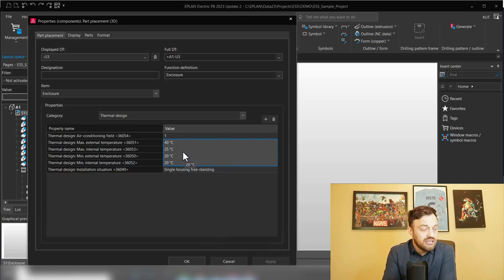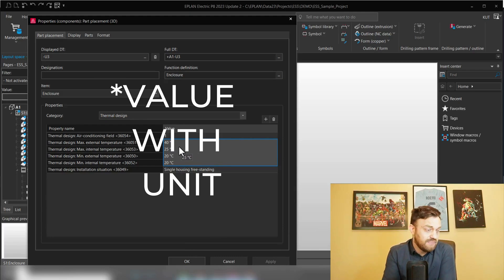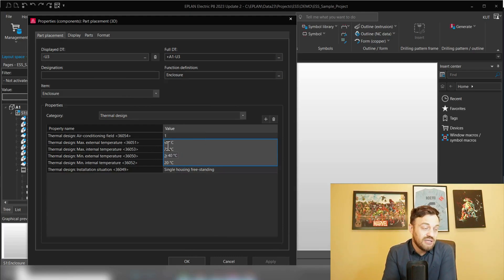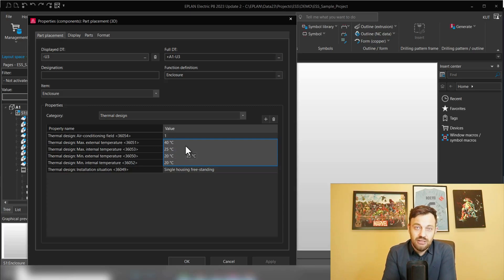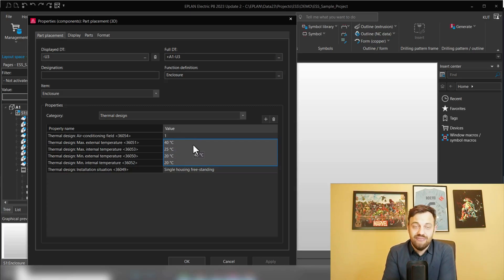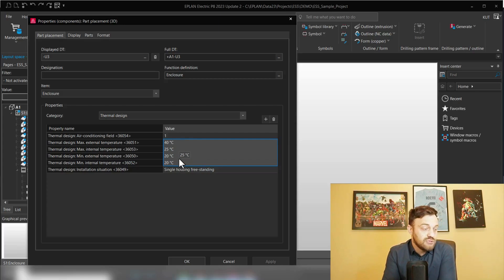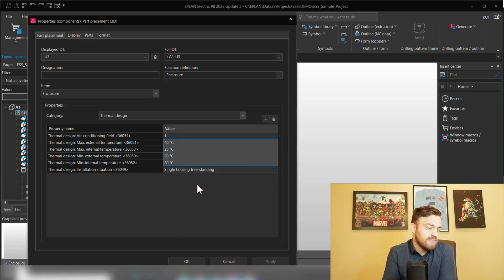Why is this important? Because depending on how the enclosure is installed, you have more or less surfaces where the heat can dissipate. Then you see the minimum, maximum internal and external temperature. It's important that you here enter the value of the temperature. If you are just entering the number, then it will calculate with degree Kelvin. So typically I would enter here degree Celsius or Fahrenheit.